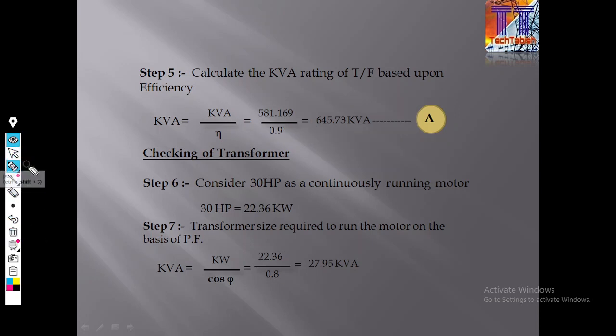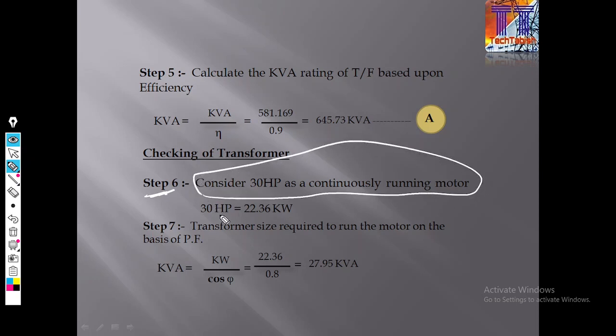In this checking, this is actually step number 6. Consider a 30 HP continuously running motor, as we have seen earlier. The power of that is 22.36 kilowatt. Okay, now step number 7, the transformer size required to run the motor on the basis of power factor. kVA equal to kilowatt upon cos phi, so the rating is 22.36 divided by 0.8. So the kVA is 27.95 kVA. This is based upon the power factor.